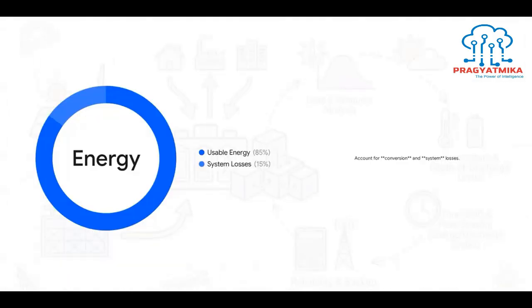And we aren't done cutting yet. You also have to slice out another 10 to 15% of that energy right off the top. Why? Well, you lose it to inverter conversions, line losses, and battery management system overhead. Your BMS needs to use some power just to monitor and balance the cells, and your inverter loses a few percentage points simply converting DC to AC power. All of these hidden taxes on your system have to be mathematically accounted for to find your true, actual capacity.